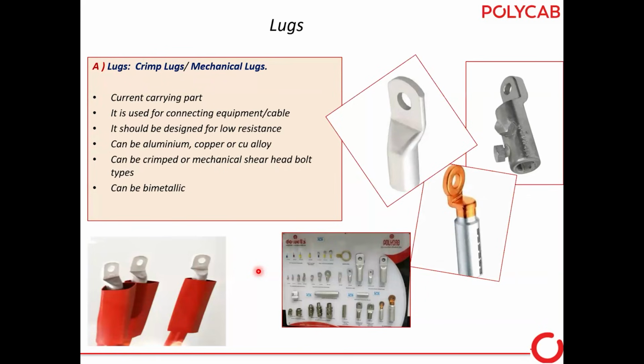Again, same way, as in the joint the ferrule was there, here in the termination lugs are required to terminate to the equipment, transformer, RMUs, or whatever it is. It is a current-carrying part, used for connecting equipment or cable. It is always designed for low resistance, and is always aluminum, copper, or bimetallic. Most people might know that Dowells, a Polycab subsidiary, manufactures our lugs and glands, and we use these lugs or ferrules in our joints and terminations.